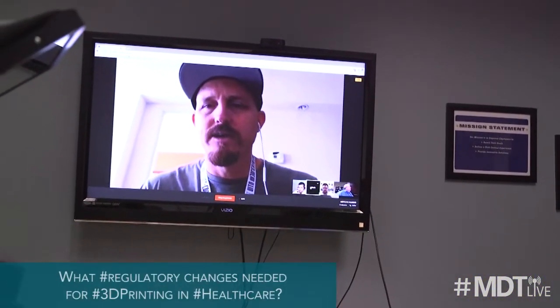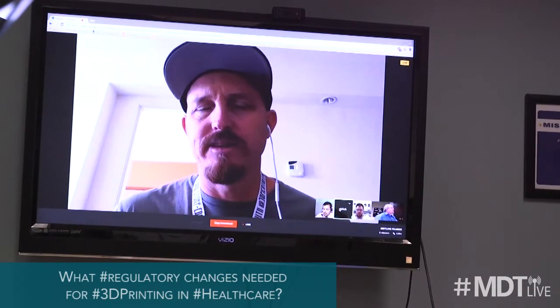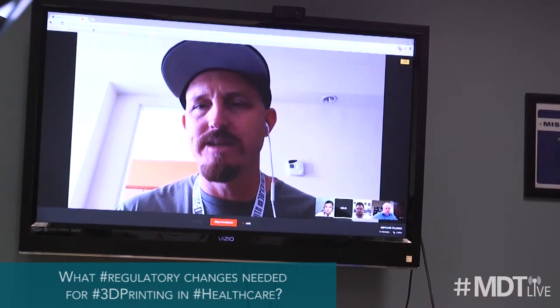If I could just ask a question to Michael. Michael, your advice on this is that once something is submitted, not to make changes. Did I understand that correctly? Oh, well, that's a good question. And to be honest, that has nothing to do with software. That's a dilemma that we face in medical device development all the time. But bottom line, in order to commercialize something, you need to have it go through design controls, assuming that it's a Class 2 or Class 3 product. If it's a Class 1 product, a lot of those devices are exempt from design controls. But nonetheless, you have to have it locked down, at least for the current generation. And then, of course, you can make changes for the future.